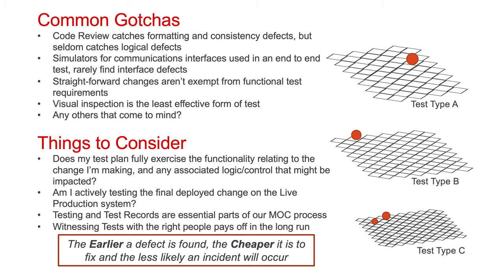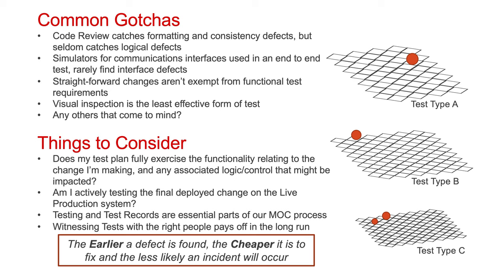Some common gotchas worth mentioning. Code review, for example, catches formatting and consistency defects, but it's not particularly effective at catching logical defects. Some people put too much faith in code review as a test method. Simulators for communications interfaces used for end-to-end testing will rarely find interface defects — in essence, you need to attach it to the real thing to be sure. Straightforward changes aren't exempt from functional test requirements; just because the change seems straightforward and requires minimal effort doesn't mean you are exempt from running a test against its functionality. Visual inspection is another gotcha, and it is the least effective form of test — visually inspecting anything is not a measure of function. There are plenty of others, but that is just a short list.